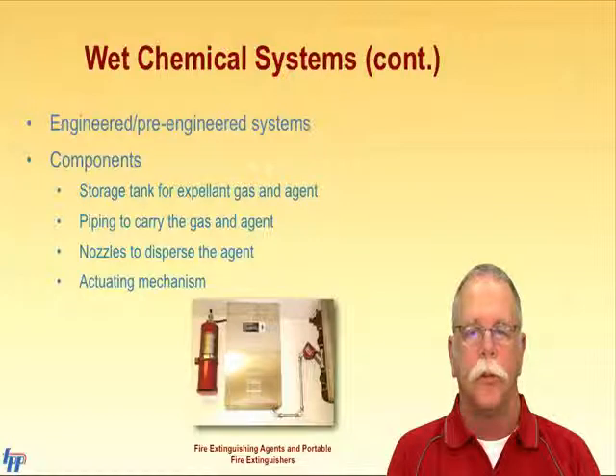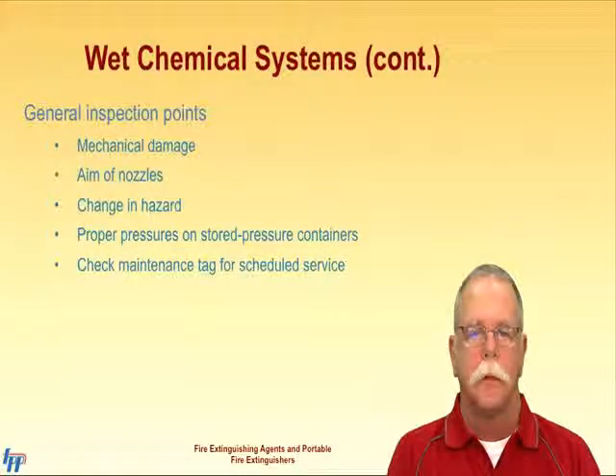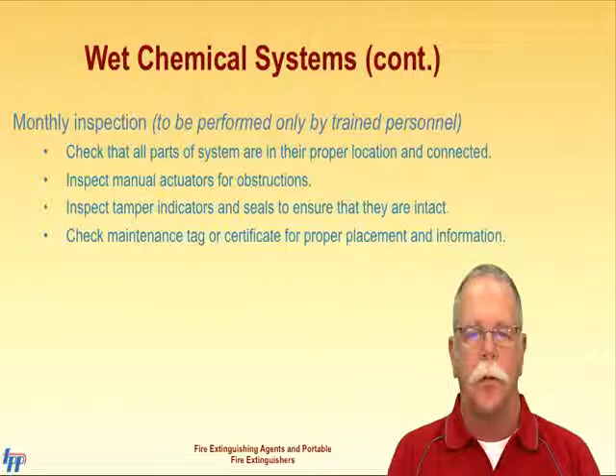Engineered systems are designed for a particular installation for a specific hazard. These systems are larger and more costly. More common is the pre-engineered system that you will find in many commercial kitchens. While on company inspections, pay attention to the system components, particularly where the nozzles are pointed. If the nozzles don't line up with the cooking device they are designed to protect, there may have been a change in the occupancy or operation. Doing so may require the occupant to have the system updated.